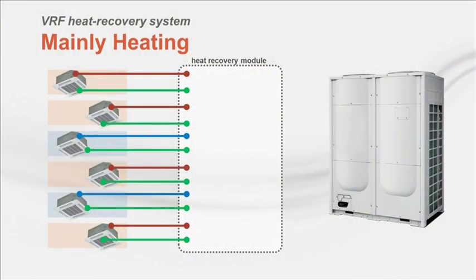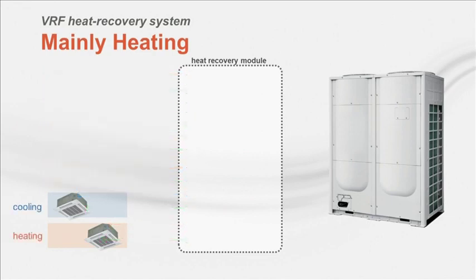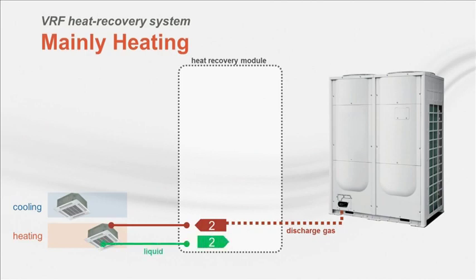Here I show a hypothetical system that has 6 equivalent zones, 2 of which are in cooling and 4 in heating. Focus on the bottom 2 zones, one requiring heating and the other cooling. The zone at the bottom requires 2 tons flow of discharge gas to satisfy the zone heating load and returns 2 tons of condensed liquid refrigerant back to the heat recovery control module. The zone above requires 2 tons of liquid refrigerant to satisfy the zone's cooling load. There it is inside the heat recovery control module. So let's steal it from my neighbor.